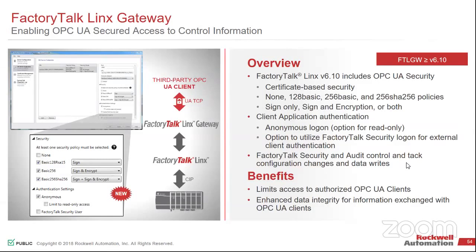So in most cases, if there's another SCADA, or some type of upper level system, or if we're looking at UA, typically that's I need to move from my business network down to my control network, and that was the kind of tie-in. I now have the ability of sending all of that data down. What we're doing with this newer version is being able to do the encryption side of it, so we can integrate into the OPC UA security.